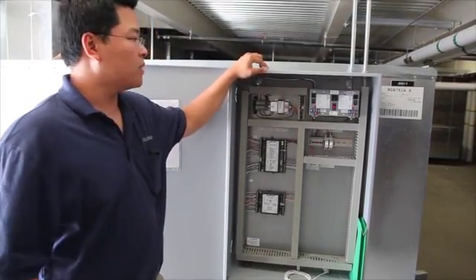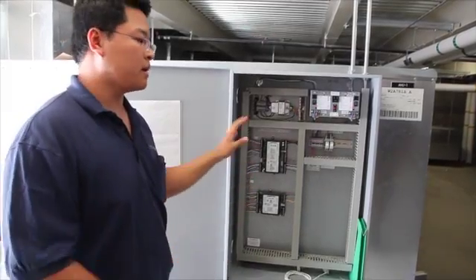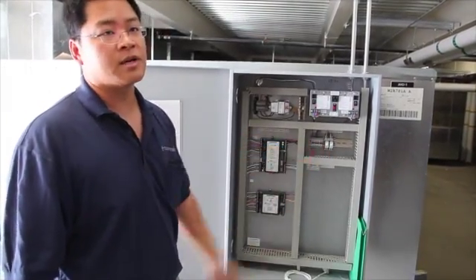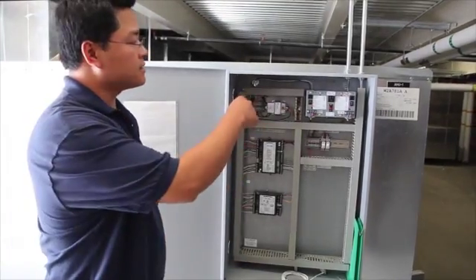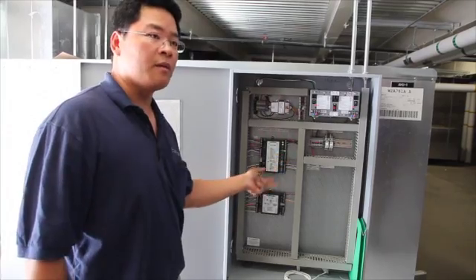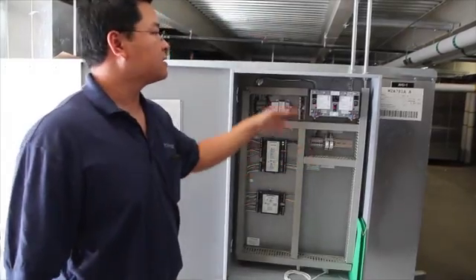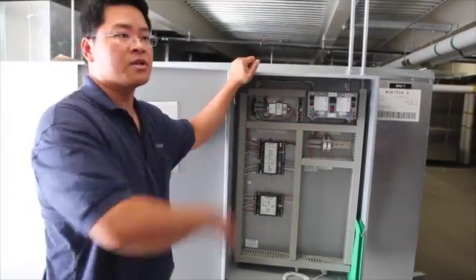This has control here. Everything else, once it's in operation, you should do it on the front end. You don't have to go up here and do anything. It's the only thing up here you can manually do is just start or stop. And the fans on the VFDs, if they go to alarm, I'm not going to be able to send out a signal from here. And when you flip this relay, it's just going to go to minimum. So even if you start this, the unit's not going to run if the alarm is tripping.